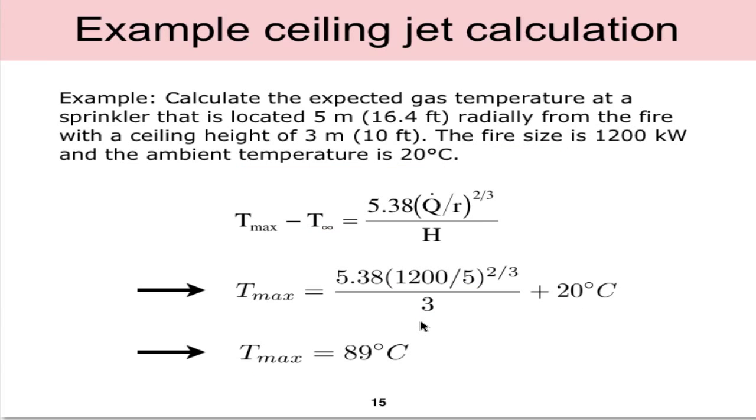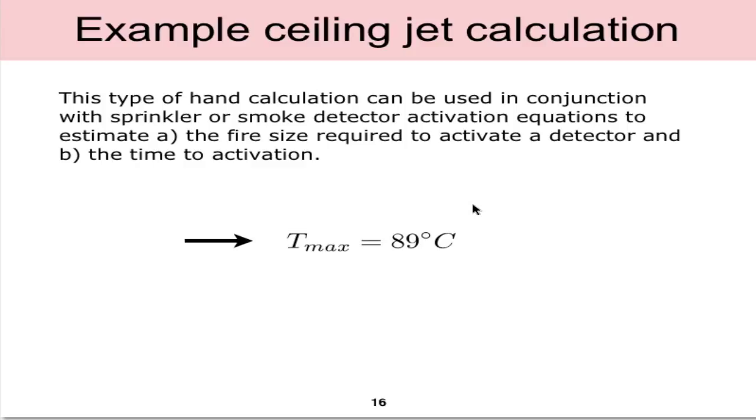This shows an example that could be used in conjunction with sprinkler or smoke detector activation equations which could estimate the required fire size and the time to activation. Now if we know a point in space and we're interested in and we know the temperature to activate a smoke detector, heat detector or sprinkler, we can actually back out the Q that's required to create to cause that temperature at that point.